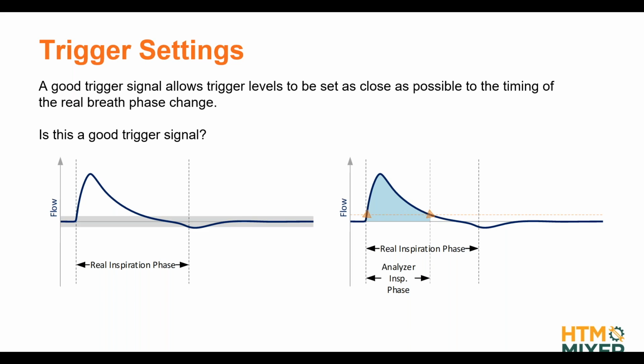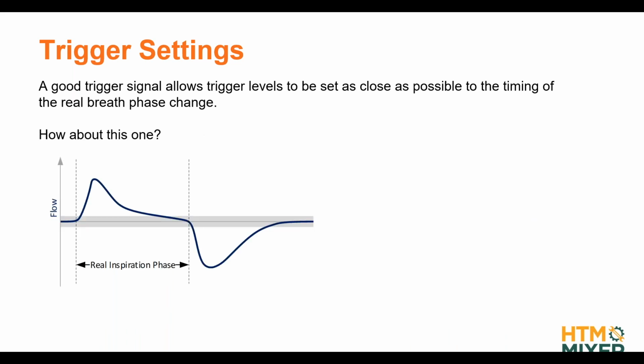But then the problem with this signal is at this transition here, it's not that good, right? The changes are marginal here in my flow waveform, and it's all within this area I can't really sufficiently trigger, right? So if I would set it to the same level as my start trigger, but on a falling edge, then my stop of the inspiration phase would be far too early, right? And my analyzer detected inspiration phase would be far shorter than the reality, and this is going to have impact on all my breath-based parameters measurement. Okay, so again, this is not a good one. The start is very good, so 50% very good, 50% it's bad. All right, second example, how about this one?